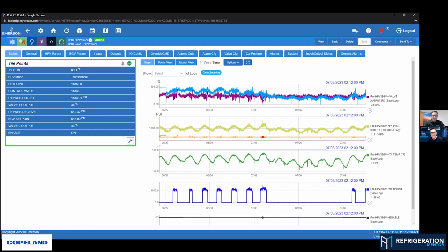As soon as you pull it up, we can see the trend here from over a week's worth of data. You can see where it's averaging through its operation, right? And to your point, Trevor, if it's fully open or fully closed and you can't explain why, you've got your trends to go back on. Okay, how does this system normally operate before this thing went silly or something happened in the system? I'm trying to troubleshoot it, right? It's like, okay, I know that my average valve percentage opening is around 40%. I walk up on it now and it's running around that, so we're running in its normal operation bands. It's a lot quicker to see what the system can trend now in the E3.